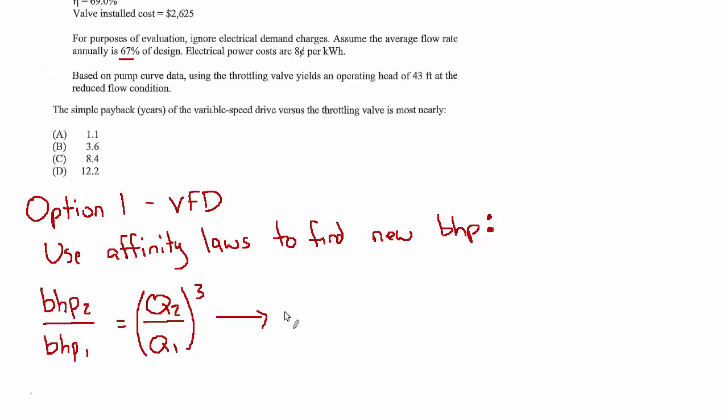So plugging in and solving for BHP2, we can take BHP1 5.8. And the ratio of Q2 to Q1, we could figure out what the actual number is and we might need to later, but we know it's 67%, so that ratio is just 0.67. And that's getting cubed. So the new horsepower is going to be 1.74. And that's still brake horsepower. So there still could be another loss in terms of electrical efficiency with which the electrical energy in an AC motor is converted to actual brake horsepower at the shaft that turns the pump.